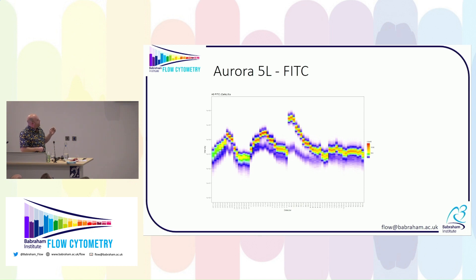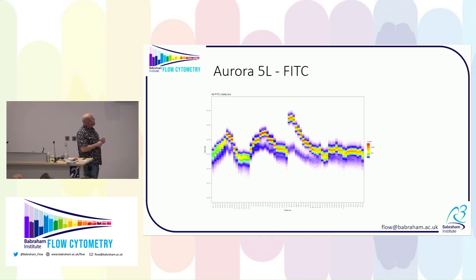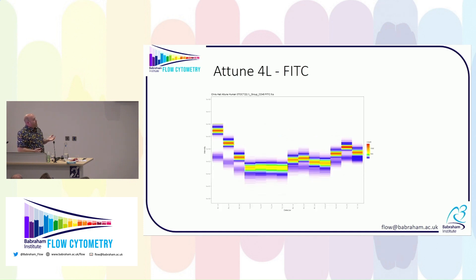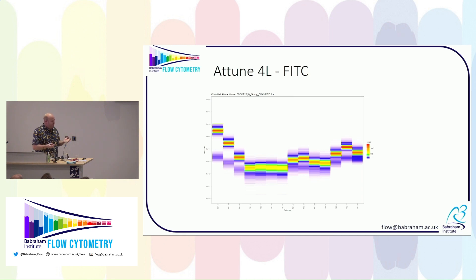This is FITC from an Aurora. We have the spectral plot: the blue laser excites the fluorophore, it emits at about 530–550 nanometers, and this is what we see — but we also see these other emissions, which is the spectral pattern. This is what we are unmixing. And looking at FITC on the Attune — a four-laser, 14-detector Attune — we have lower density data, but we still have a pattern. We have the 530 emission from the blue laser, a little bit from the violet, and possibly a little from the red. It's still a spectral pattern.